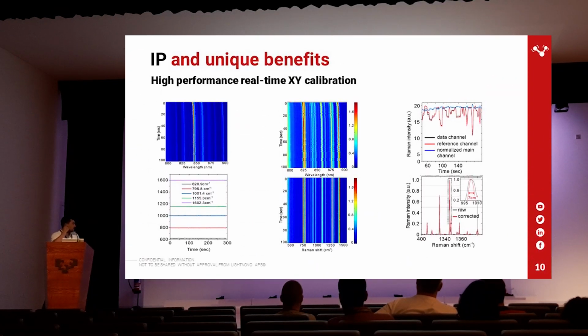So basically, as you can see here, the calibration, the X and Y calibration, intensity-wise and spectrally-wise, is performed in real time. And we can get very stable Raman spectra, as you can see here, even with unstable lasers. And this is due to the presence of reference channels. So basically, every spectrum, every acquisition is corrected and recalibrated in real time in the embedded software on the device. And you already get corrected data.